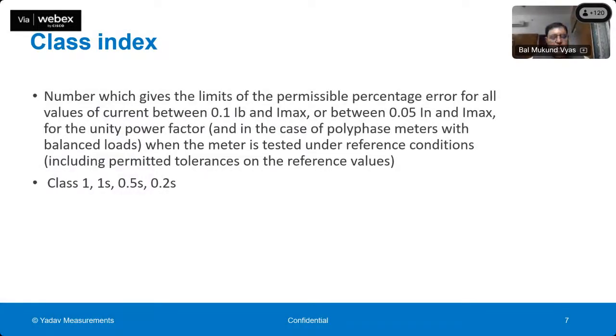Now, it is very important to understand what we mean by class index. When we say class 1 meter, most of our houses are connected with class 1 accuracy meters. In general, people will understand that a class 1 meter gives billing accuracy of plus minus 1%. But there is a very important difference to understand. What is class 1? When class 1, or class 0.5, or class 0.2 is mentioned, it means that the meter is accurate up to plus minus 1% from Imax to 0.1 Ib, or 0.05 In to Imax for a CT operated meter, at unity power factor, when the meter is tested under reference conditions only. So this is very important. This accuracy class is defined under reference conditions.